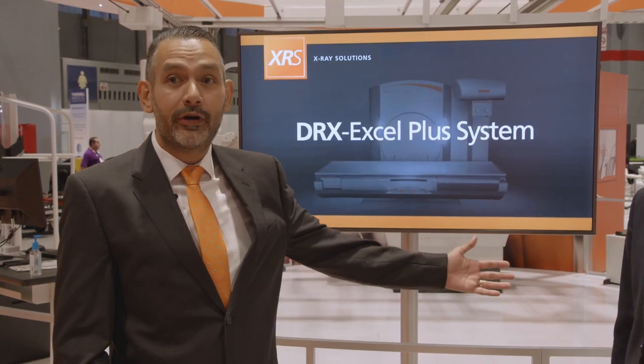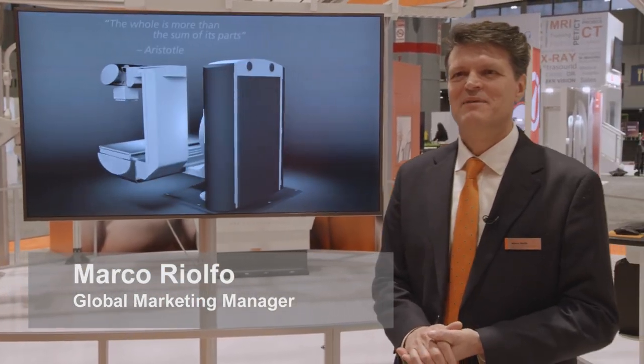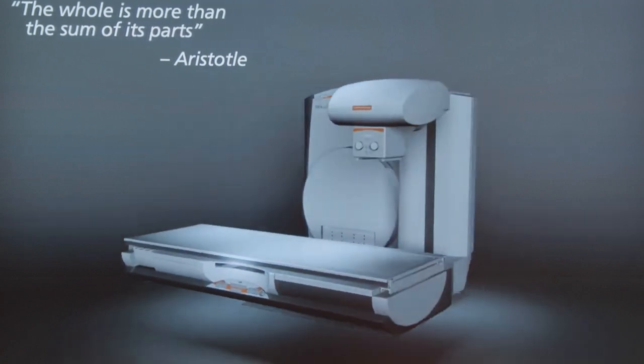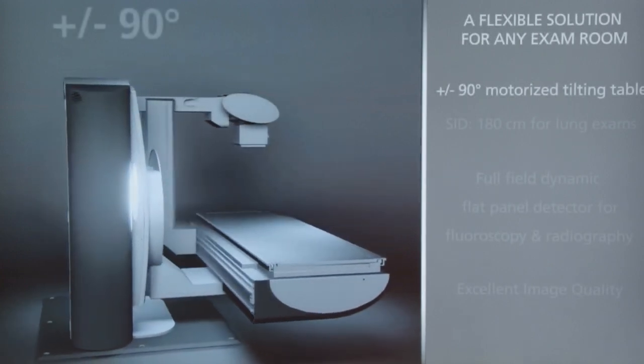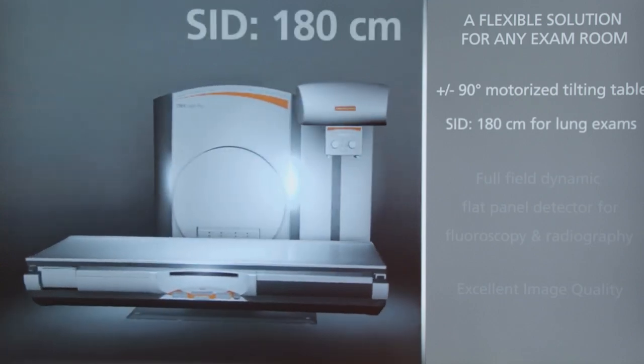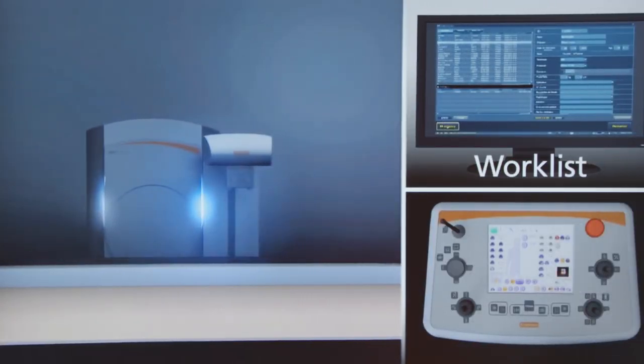We've also improved our DRX-Excel Plus. The DRX-Excel Plus is already a high-performing unit, delivering both radiography and fluoroscopy. Our new improvements make it even more versatile and easier for the radiographer. Our new ADAM console brings LLI auto-stitching capability to the system, and the system has a redesigned graphic interface that makes it easier and faster to use — as simple as a smartphone.